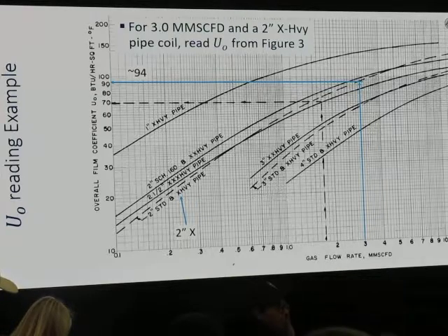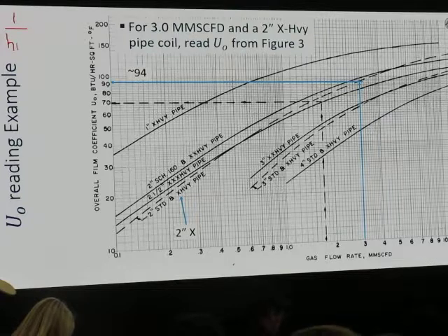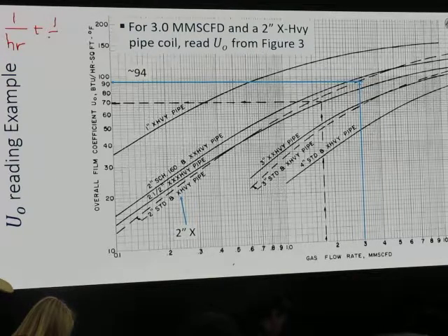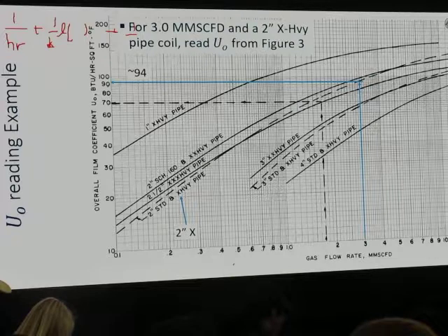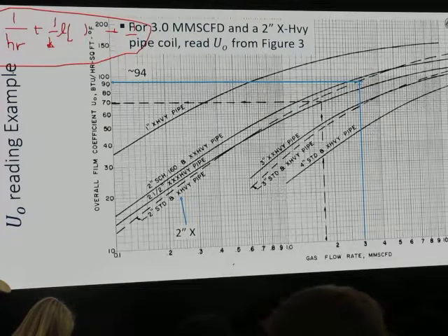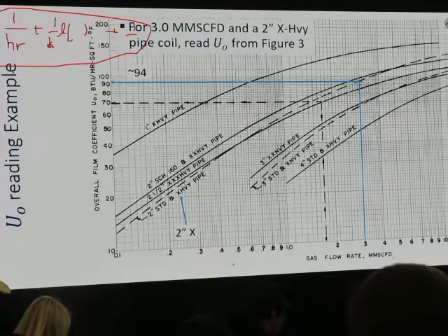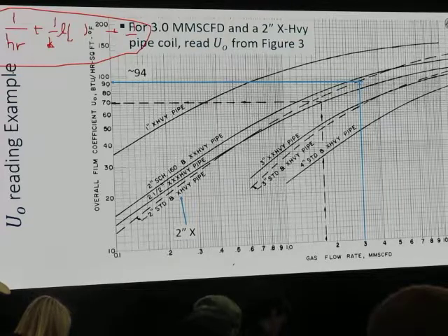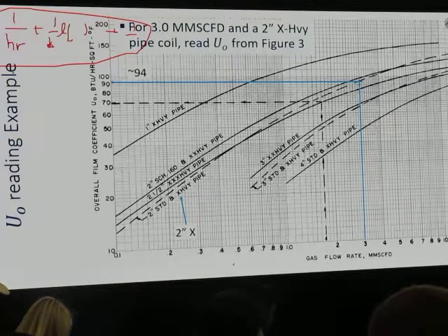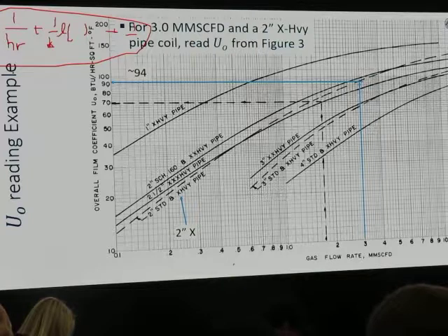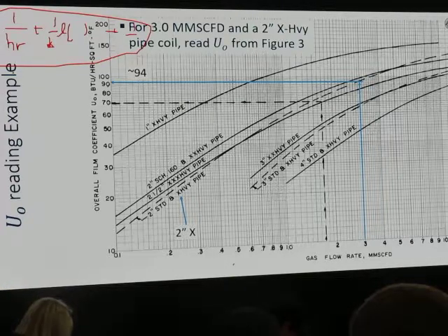What happened is the U value is calculated from 1 over h, like combination of convective heat transfer, plus 1 over k log of something over something, plus 1 over h. I know that's not a full formula, but what I mean is there are three parts that resist the heat movement. The big or thin pipe doesn't matter. The heat transfer resistance due to the pipe being a little bit bigger is not as much as the heat transfer resistance that comes from the gas that gets slower. So if gas moves slower, it transfers less heat. That matters more than the pipe is bigger. I mean thicker, a little bit bigger. So the thickness of the pipe, it matters but not much.